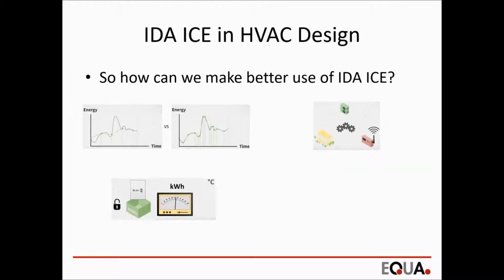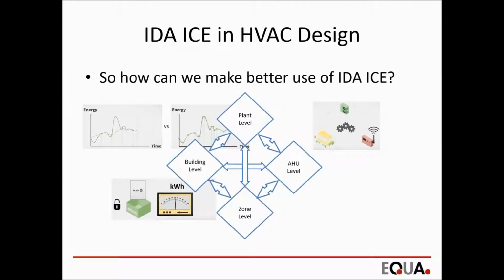However, what few people know is that in IDA-ICE you have an inherent hierarchical structure of control. IDA-ICE basically has levels of control: a building level control, which we call a supervisory level control, a zone level control, and a unit level control. These building level, zone level, and unit levels are able to communicate together and send signals to each other.